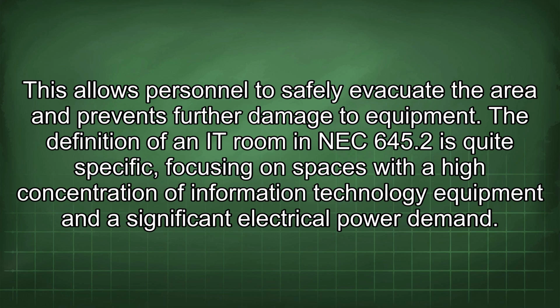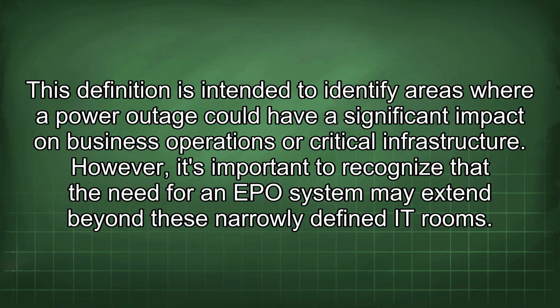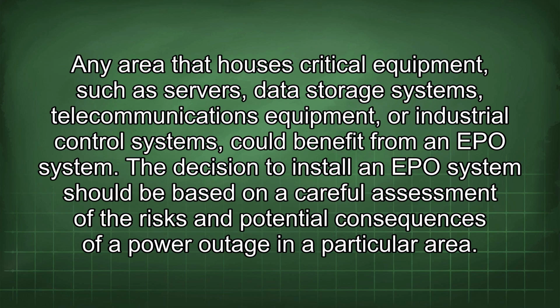The definition of an IT room in NEC 645.2 is quite specific, focusing on spaces with a high concentration of information technology equipment and a significant electrical power demand. This definition is intended to identify areas where a power outage could have a significant impact on business operations or critical infrastructure. However, it's important to recognize that the need for an EPO system may extend beyond these narrowly defined IT rooms. Any area that houses critical equipment, such as servers, data storage systems, telecommunications equipment, or industrial control systems, could benefit from an EPO system.